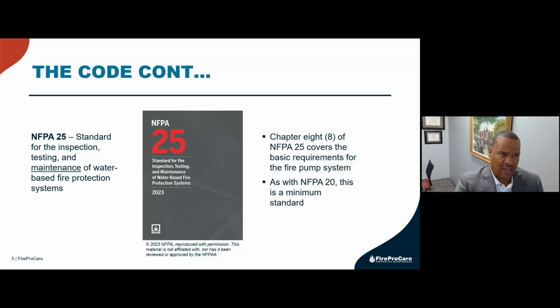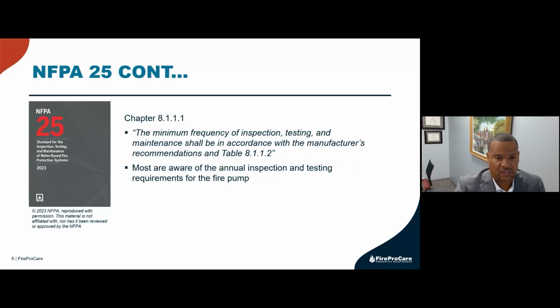This section is going to be the most important part of my presentation because it is all about code. What I'm talking about today is the minimum requirements on what you need to do to design your fire pump controller and to design and build your preventive maintenance system. What I found interesting, in my 30 years that I've been doing this, is that I didn't realize that customers needed to comply with NFPA 25. There are some locales that push it, and there are some savvy people that drive it. However, they never consult with the fire pump controller manufacturers, which you'll find later is very important. So let's continue. Chapter 8.1.1.1 talks about the intervals on how often you should inspect, test, and maintain your fire protection system.